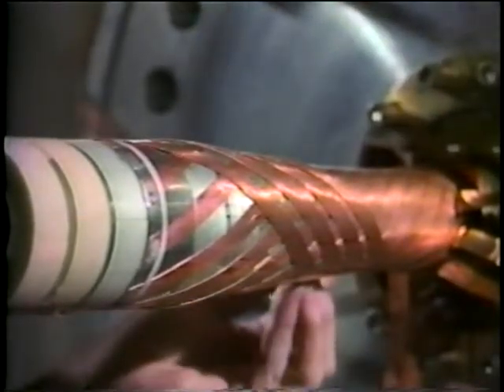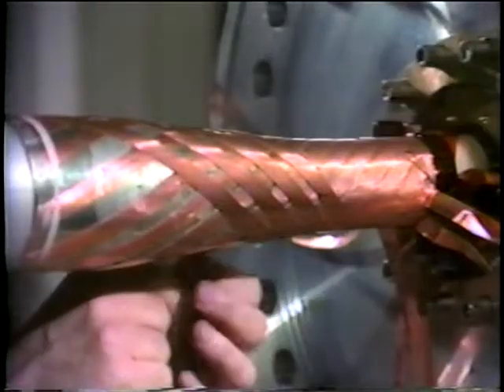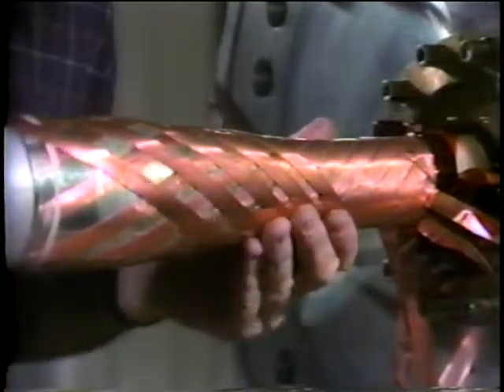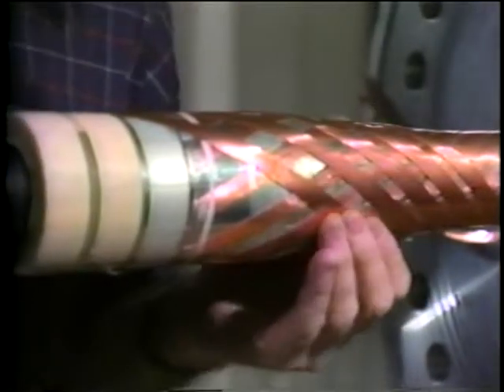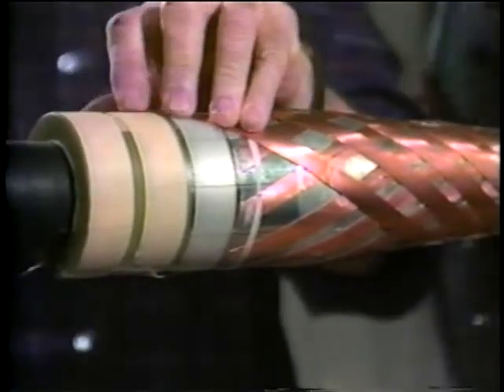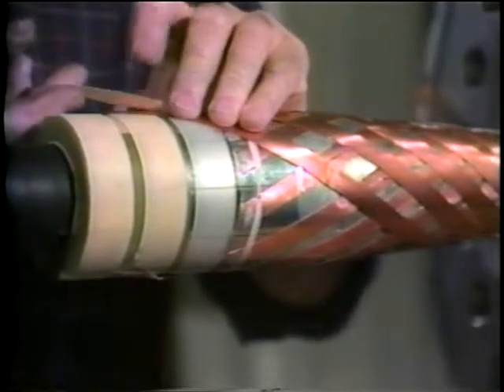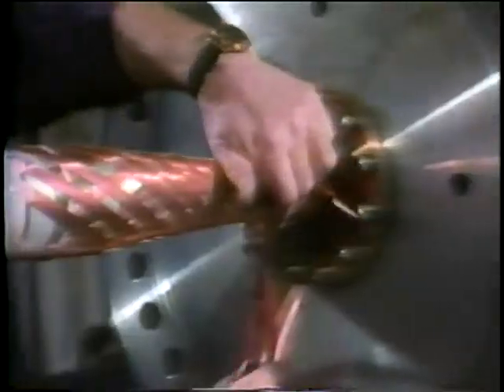The superconducting cable has both inner and outer conductors, which are designed to carry equal currents but in opposite directions. Each conductor consists of four layers of tape, a pair of superconducting tapes and a pair of copper tapes. Copper tapes are provided to carry current if for some reason the superconducting tapes pass out of the superconducting regime. This can happen, for example, when the network is accidentally short-circuited and very heavy currents, perhaps 10 times the normal value, may flow briefly. The completed cable end awaits the next step in the assembly of the termination.